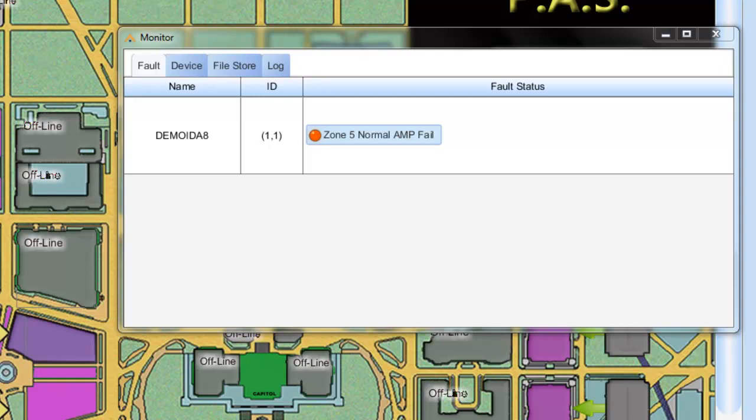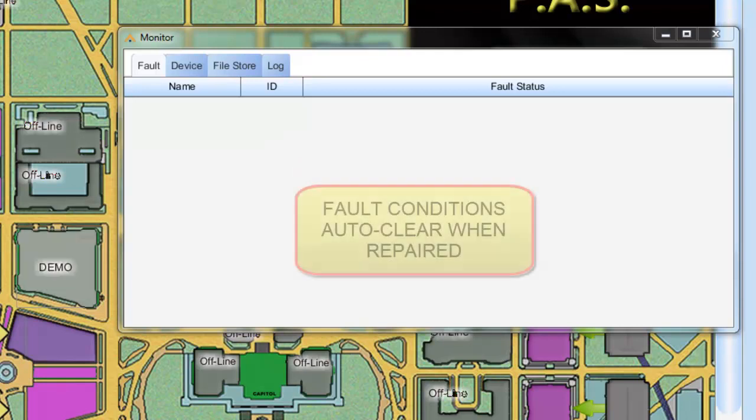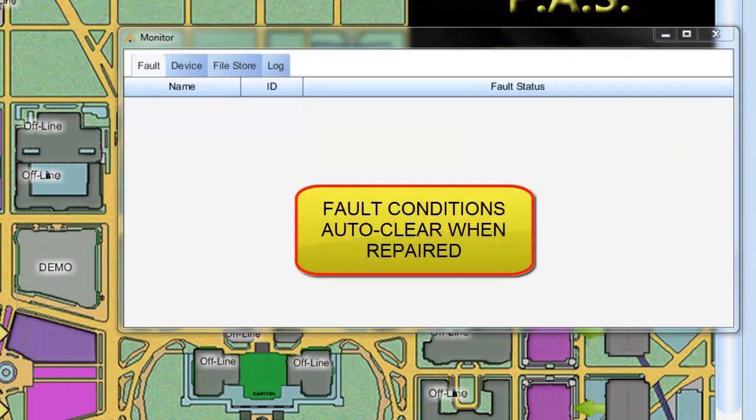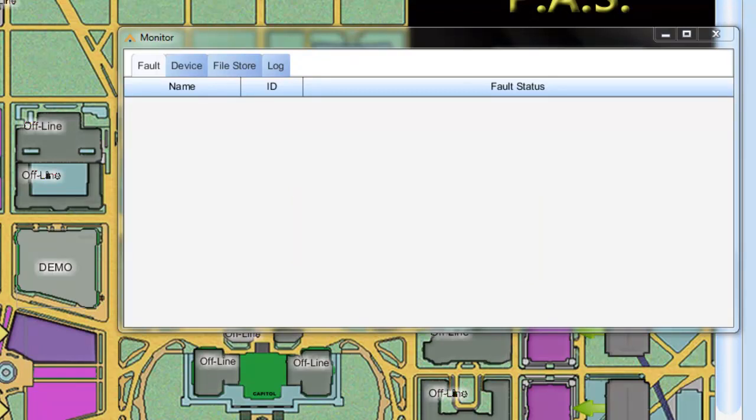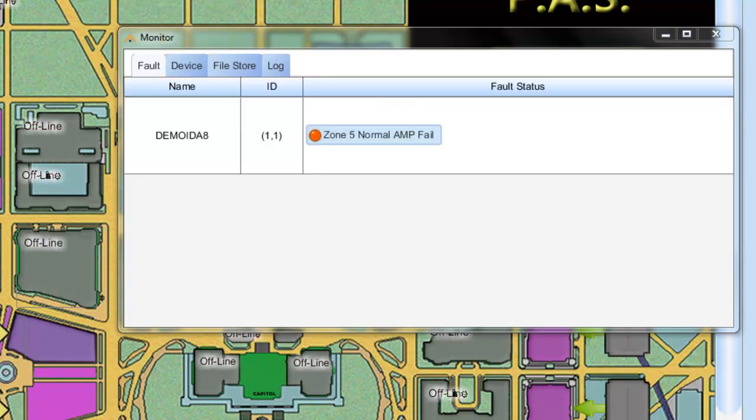All right. So now I will plug this back in. This is the line level output of the IDA8 going to the input of the amplifier. There you go. All right. Now I am going to unplug the 70 volt amplifier output coming back into the IDA8 system or the amplified return. So I just unplug this now. There you go. The trouble comes in. And as you can see it says the same thing. It's the same amplifier error on the same circuit.